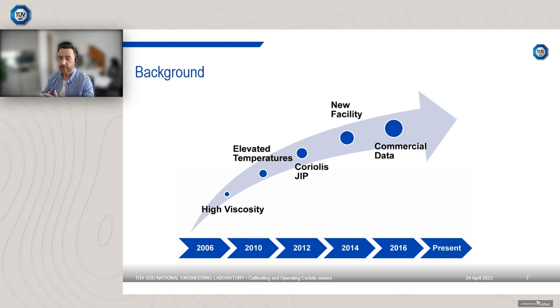So this was operating up to 200 to 300 centipoise, so medium-high viscosity. We started to recognise there potentially was a requirement for elevated viscosity, so even higher. However, our facilities at the time could only go up to around 200, 300. I then started in 2008. One of the first projects I was involved in was upgrading our facilities to accommodate high viscosity fluids. So we redesigned our national standards oil flow facility to accommodate high viscosity fluids up to 2000 centipoise.